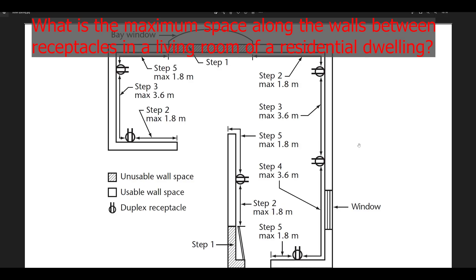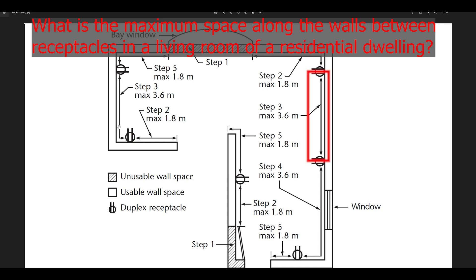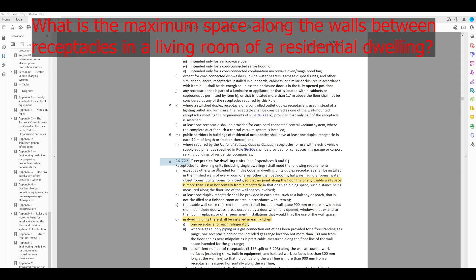What does that mean? Here's a visual. You can't have more than 1.8 meters from anywhere along the wall to the closest receptacle. From the edge you can measure 1.8 meters and put an outlet. But between each outlet you can actually have up to 3.6 meters, because even if you were to drop a pin right between them, you would still have 1.8 meters to the closest receptacle. So it's worded in a tricky way: 3.6 meters between outlets, and no farther than 1.8 meters from any point on the wall to a receptacle.